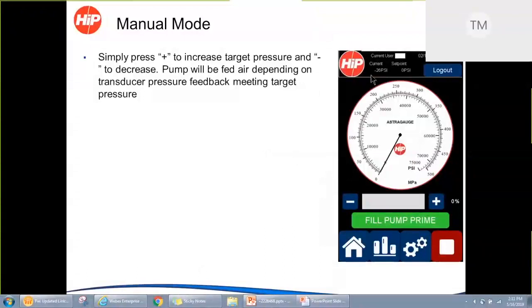You'll also notice there are some buttons on the bottom of this screen. There's a house, that's the home screen, which is this manual run screen. The chart will get you into our automated pressure test function where you can track pressure versus time data. The gears are your setups, so there are various machine parameters and test setups that you can perform. The red stop button is just what you'd think it would be. It shuts the air pressure off to the pump, and it'll bleed the pressure down to 0 psi.